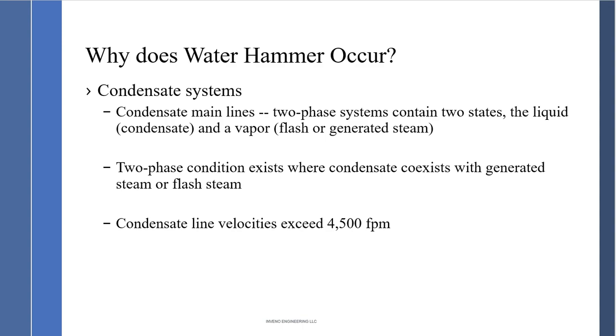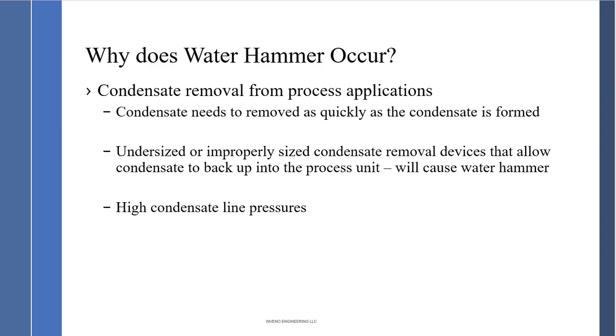The other thing with condensate lines, we need to design them. If you're not going to have a proactive steam trap maintenance program, then we have to upsize the condensate lines for the additional steam that's going to be allowed to flow into the condensate line so we don't exceed 4,500 feet per minute. Condensate needs to be removed as quickly as it is formed from the process applications. Process applications in steam, 99.5% of them are designed for condensate to be removed as quickly as possible. They're not designed for flooded conditions.